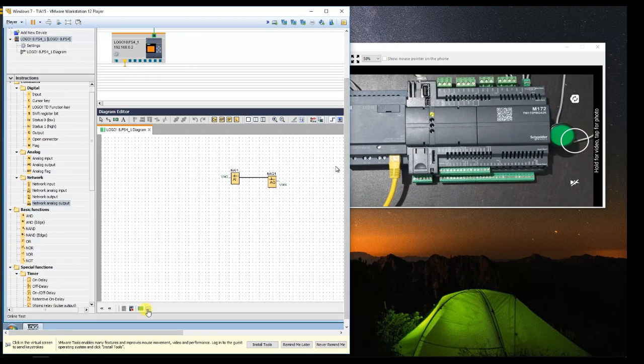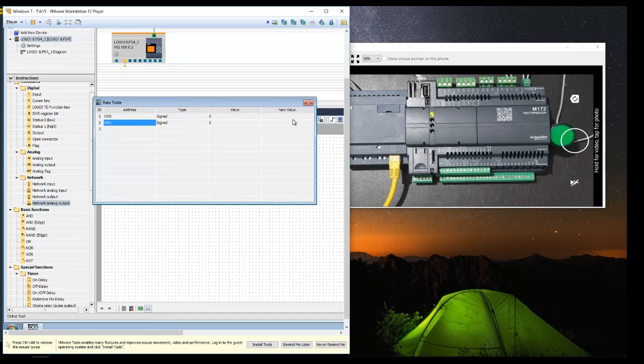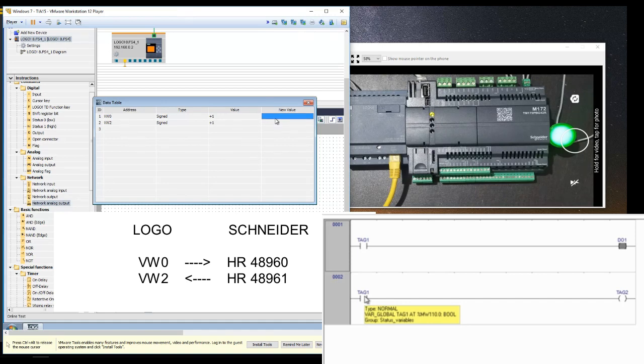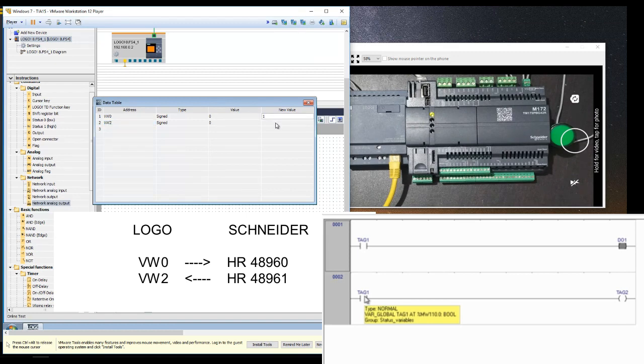Now let us check our addresses in the data table. You can observe that as soon as I am changing VW0, it is changing the output. At the same time, we are receiving the status from address 48961 that we have read on address VW2. By this method, you can define multiple addresses on a single connection.